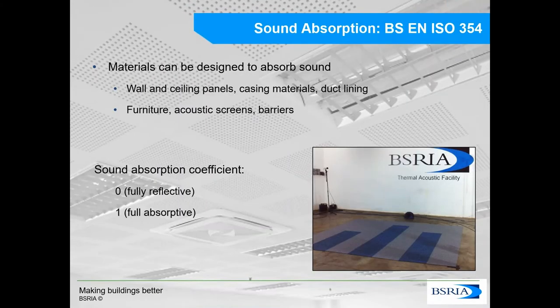The second type of measurement is sound absorption, determined in accordance with BS EN ISO 354. Different materials can be designed to absorb sound — wall and ceiling panels, duct liner materials, and screens and barriers used in the built environment. A sound absorption coefficient is determined, where zero is fully reflective and one is fully absorptive. An acoustic panel used on a wall would typically have a sound absorption coefficient of around 0.8 or 0.9.